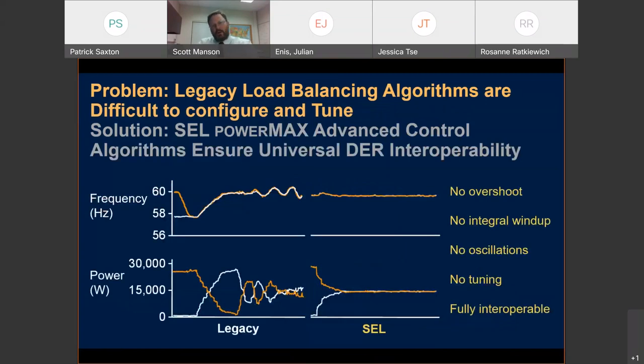Another challenge we took on that you can only do with distributed controls that are everywhere, which happens to be a relay, is advanced control strategies. Here's an example of an energy packet controller out of an SEL relay. On the left-hand side, you have two 30-kilowatt generators that were paralleled in the load sharing algorithm from their onboard load sharing control, which really hasn't changed. Even today with digital controllers, they use the same antiquated techniques designed in the 60s, 70s, and 80s.